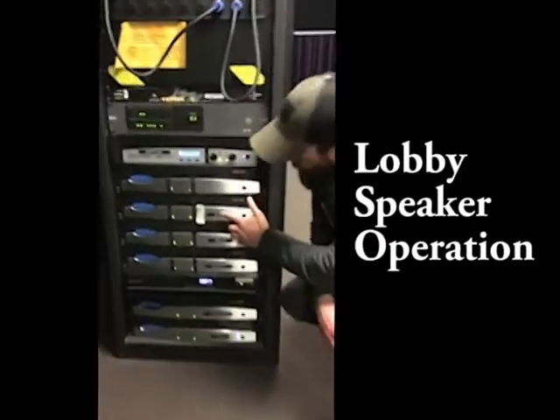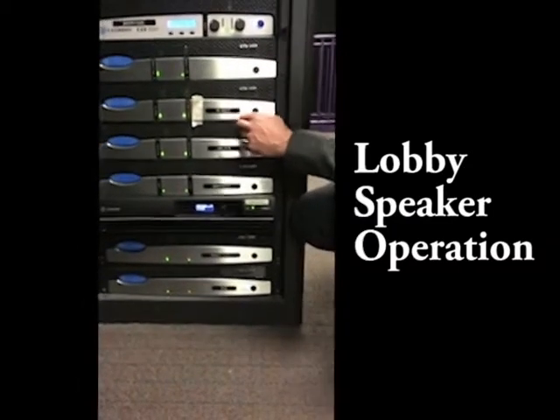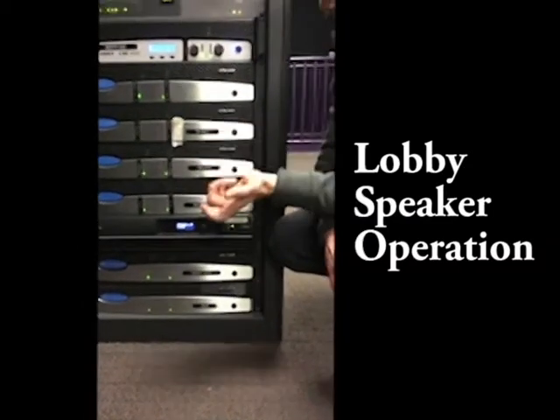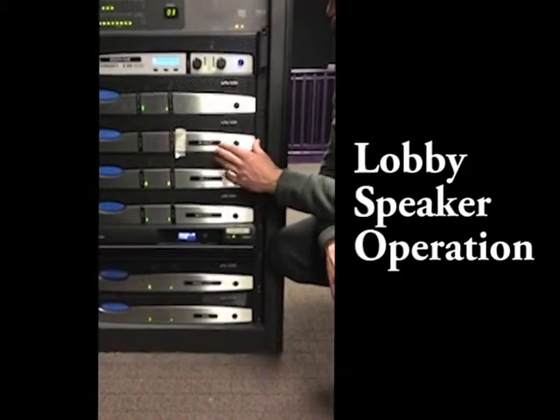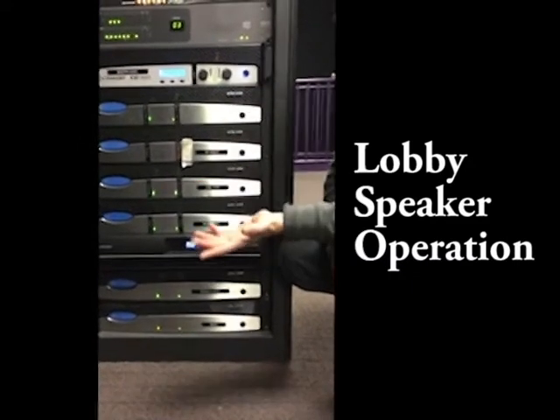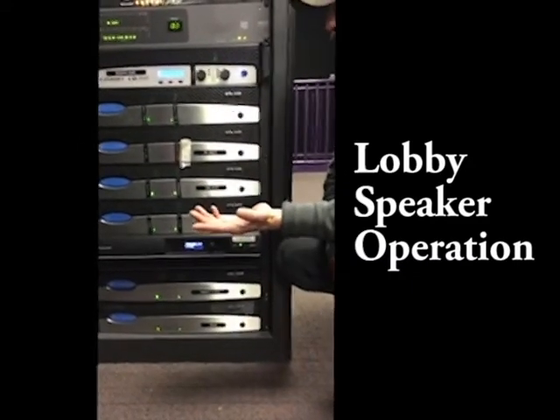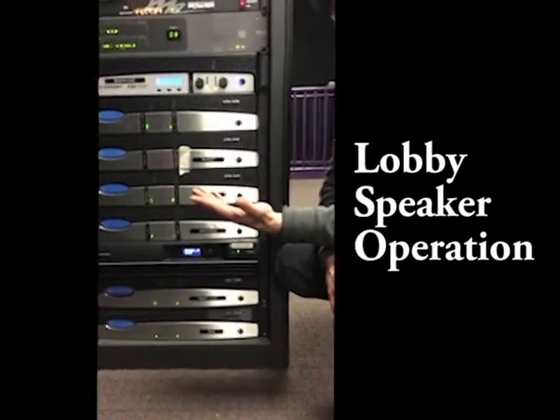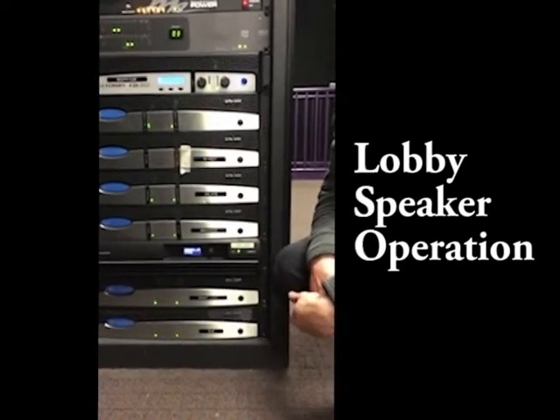Those are 70-volt speakers, the lobby speakers. If we want to turn those off, we're simply going to turn this amplifier off that feeds the lobby, and that's how we make those speakers dead, so that it's nice and quiet out in the lobby and we still have sound going on inside the room.